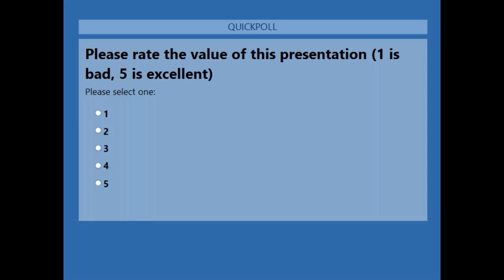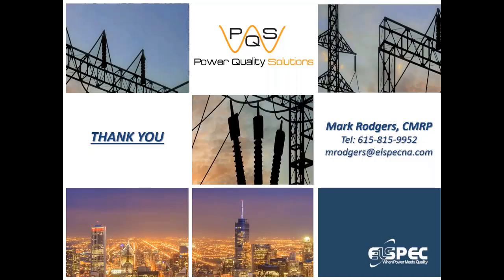Our system itself is connected internally in delta, but we can connect to Y, obviously. And for a medium voltage system, we recommend using a delta to delta transformer to step it down to that 690 or 600 volt, where at all possible, so that there's no phase shift that's induced, but we can also account for that phase shift internal to our controller if that's something that's required.